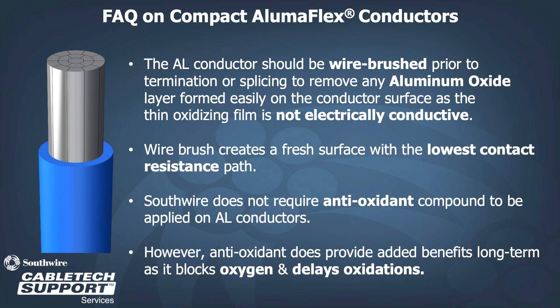The aluminum conductor should be wire brushed prior to terminations or splicing to remove any aluminum oxide layer formed on the conductor surface. This layer is not electrically conductive and should be removed to create a fresh surface with the lowest contact resistance path. It is not our recommendation to require an antioxidant compound to be applied on aluminum conductors; however, it does provide added long-term benefits as it blocks oxygen and delays oxidation.